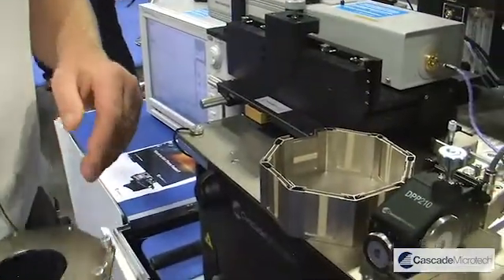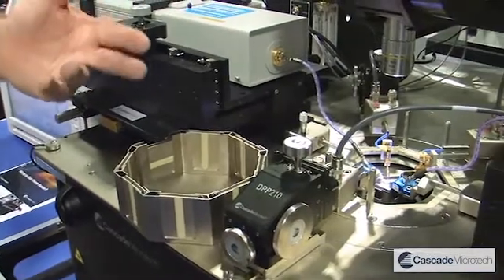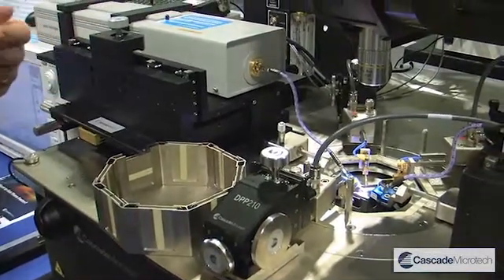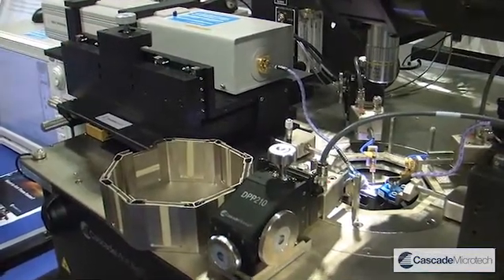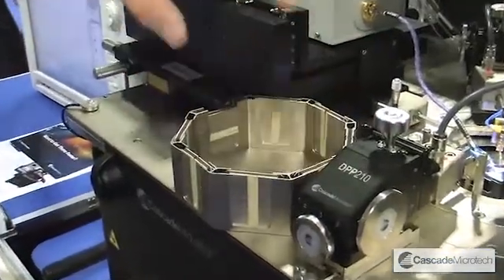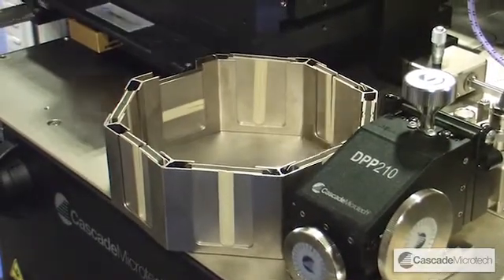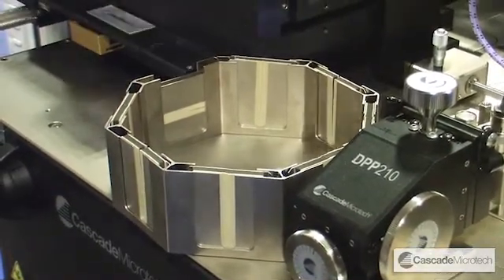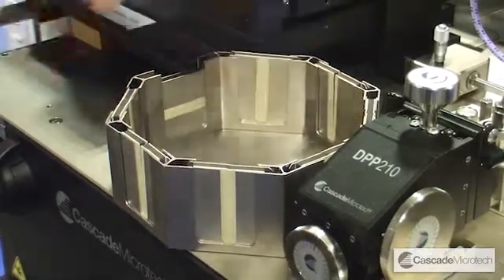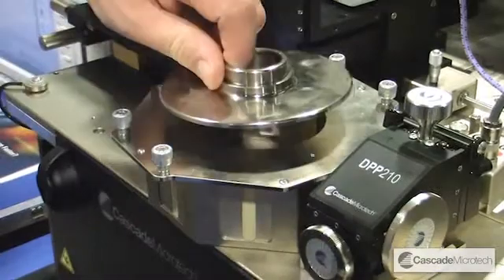When we use this machine to go to low temperatures or in an environment where we want to keep it free of light or EMI emissions, we tend to use an assembly that we call a top hat. This enables us to have the system fully sealed up. At the same time we can have it dark or light without actually physically opening everything up — we just use the sliders that move around. It's the top of the machine, and the microscope objective comes in through here.